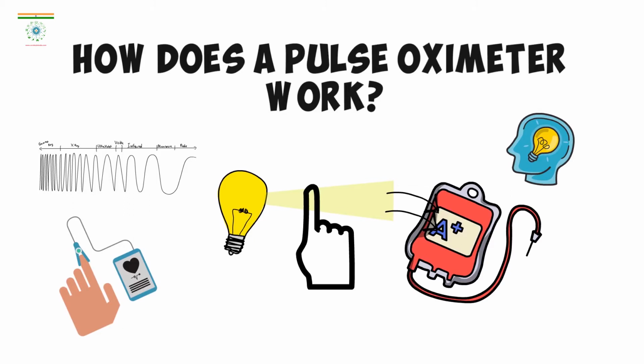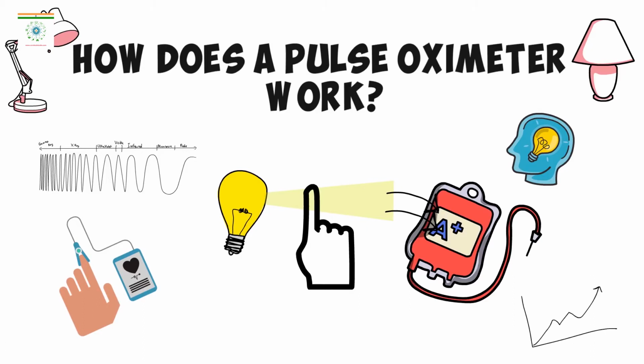The internal circuits and processing components of the pulse oximeter do some calculations as well. That is because the device has to compensate for ambient light, so for example the light in your room or from the sun. It also has to compensate for the size of the finger and for the absorbance of the rest of the tissues. The device has a reference curve that is saved into its memory, and it uses this as a way to calibrate incoming readings and to normalize them so that you can get an accurate reading. And this helps to increase the precision of the results that it provides.